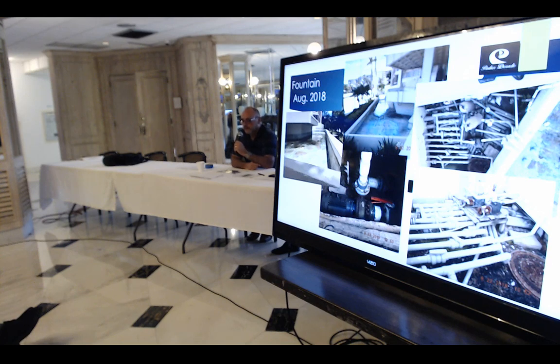We cannot leave the building without an emergency generator, new or old. That's why the shutdown for converting between the old and new generator has to happen in just one day. The generator, even during a hurricane, is a life safety system, so you never turn off your generator. Basic life safety in the building includes emergency lights, emergency exits, sprinklers, and one elevator.